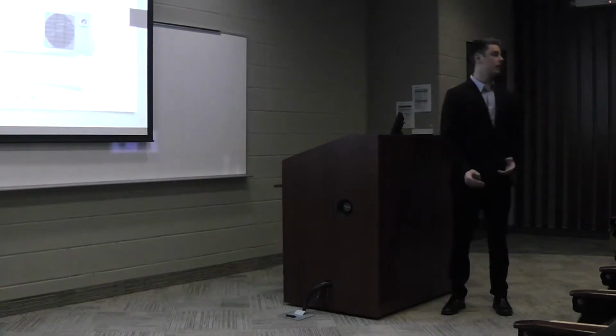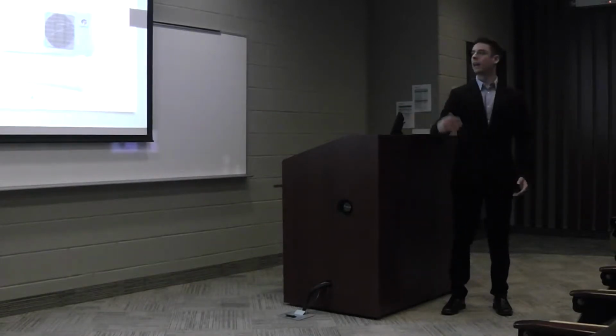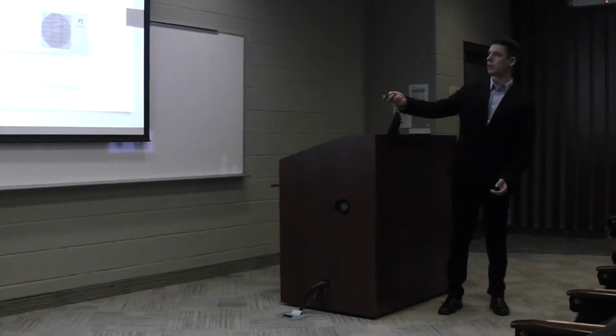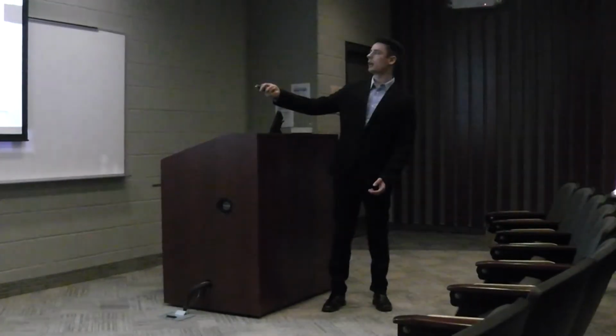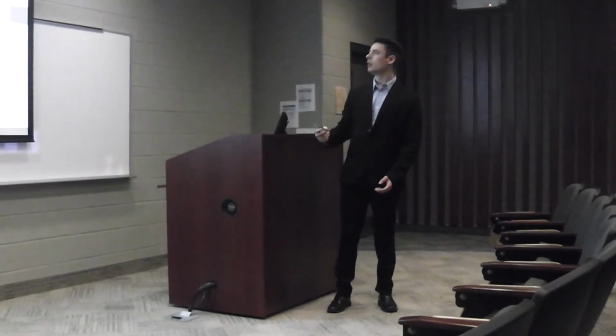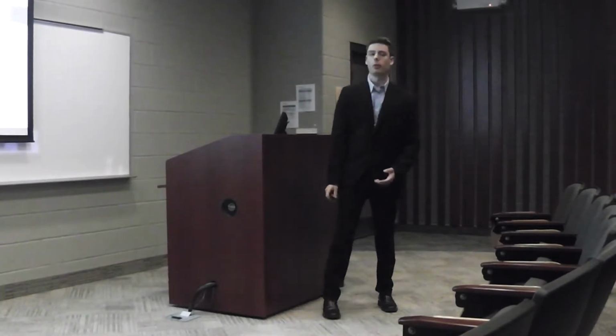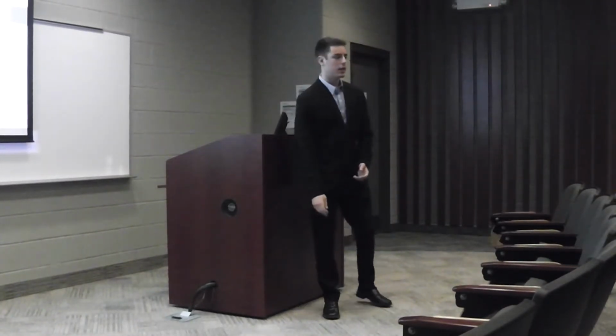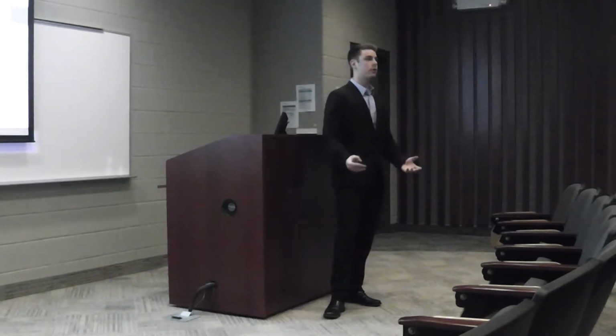To compare that to the systems in place, yes, we have two systems that have the capacity to adequately heat the space, because the in-floor system has 34,000 and the two ductless mini splits have a heating capacity of 24,000. So to make a recommendation, I'd have to compare which one is more efficient to run.